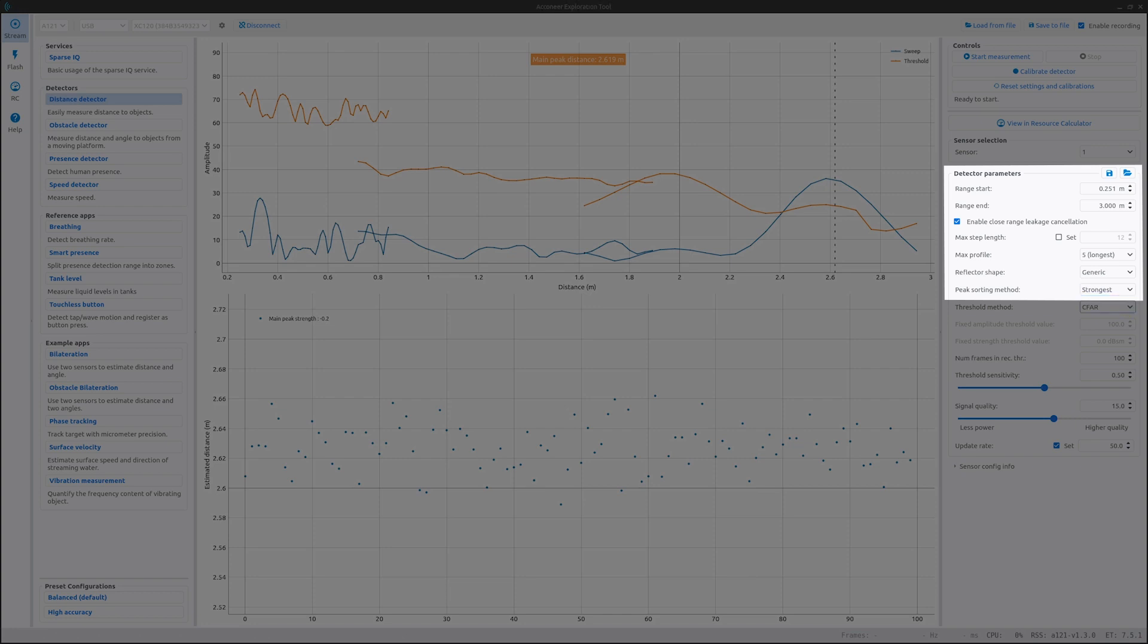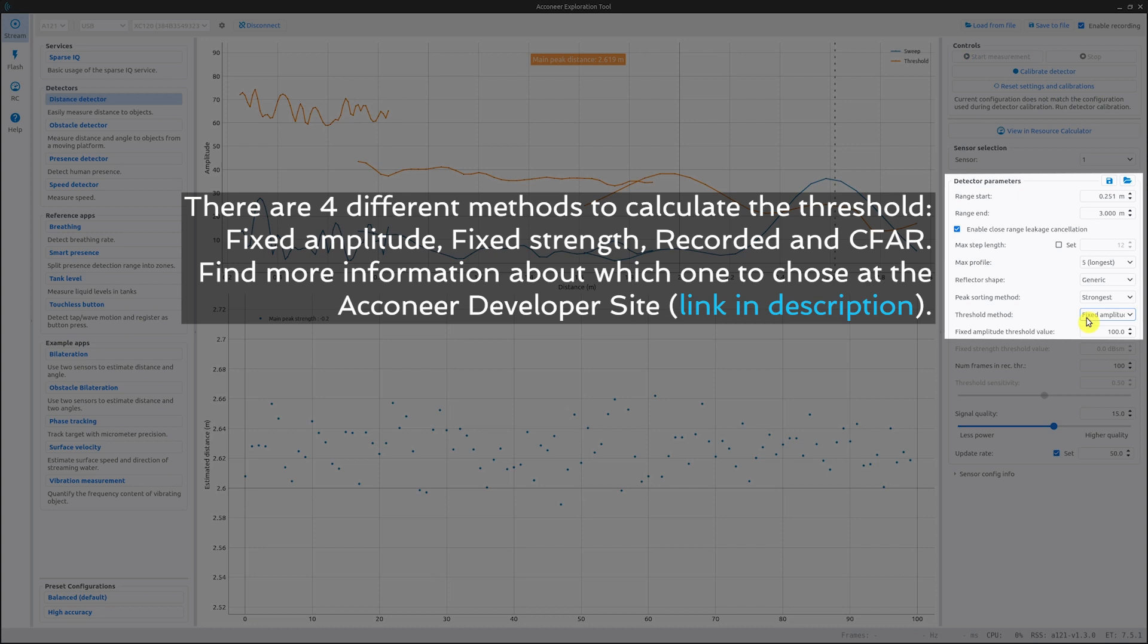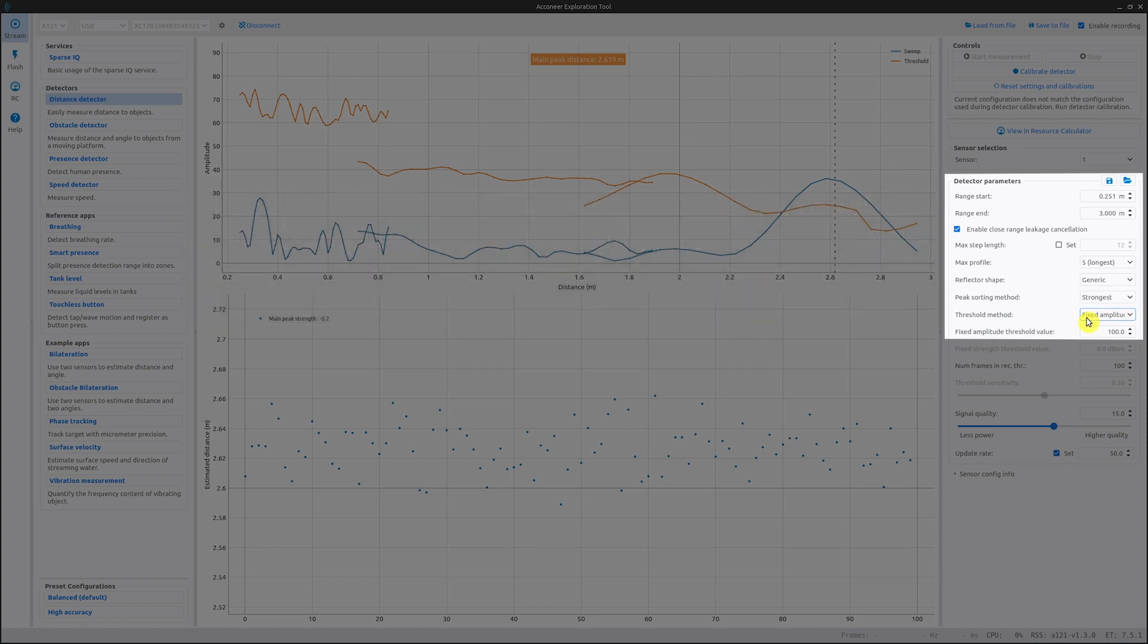Now we have come to the threshold methods. If you click the drop-down menu, you will see four different options. The first one is fixed amplitude threshold. This sets a fixed amplitude threshold over the entire range. This threshold does not have temperature compensation built in. So when temperature increases, the amplitude of the signal and noise will decrease. So for use cases in environments with fluctuating temperatures, one would instead want a threshold which compensates for decreasing SNR at higher temperatures.